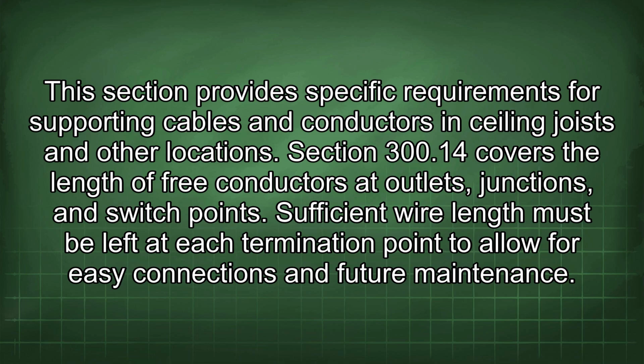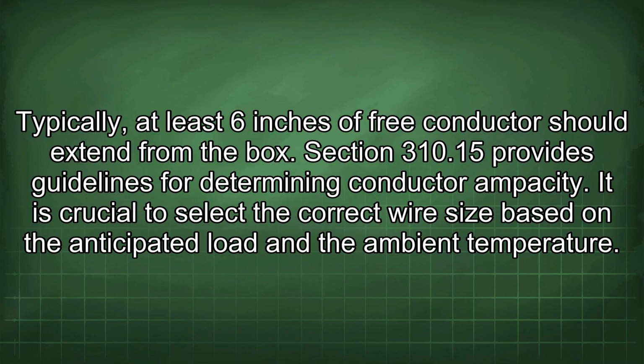Section 300.14 covers the length of free conductors at outlets, junctions, and switch points. Sufficient wire length must be left at each termination point to allow for easy connections and future maintenance. Typically, at least 6 inches of free conductors should extend from the box. Section 310.15 provides guidelines for determining conductor ampacity.